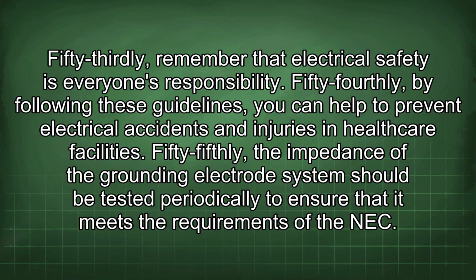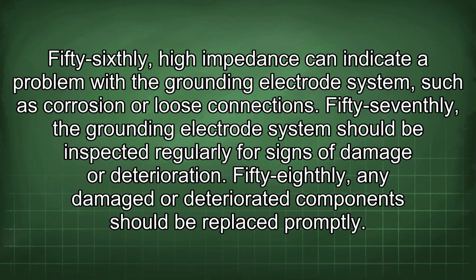55thly, the impedance of the grounding electrode system should be tested periodically to ensure that it meets the requirements of the NEC. 56thly, high impedance can indicate a problem with the grounding electrode system, such as corrosion or loose connections. 57thly, the grounding electrode system should be inspected regularly for signs of damage or deterioration. 58thly, any damaged or deteriorated component should be replaced promptly.